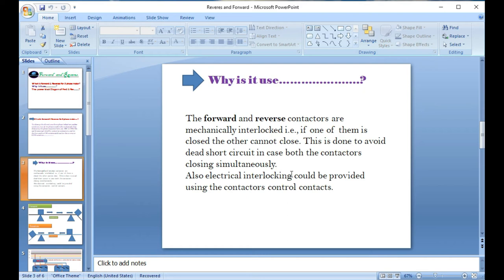If both contactors are connected to power at the same time, it can cause a serious incident or accident to your devices. To recover from this risk, you need the interlock system. The interlock for the contactor ensures that when forward is running, no person can force a switch to reverse, and when reverse is running, no one can force it to forward. Electrical interlock is also provided using auxiliary contact control — this is a major safety feature for any kind of industry.